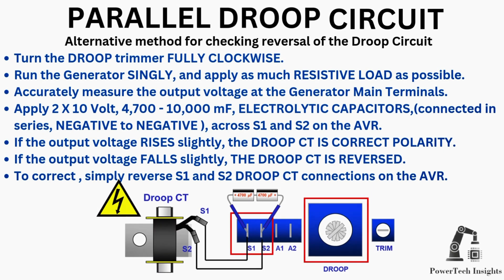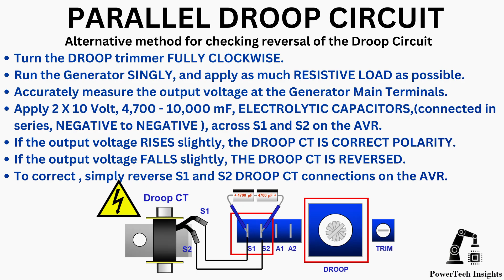Alternative method for checking reversal of the droop circuit. Turn the droop trimmer fully clockwise. Run the generator singly and apply as much resistive load as possible. Accurately measure the output voltage at the generator main terminals. Apply 2×10V, 4,700 to 10,000 microfarad electrolytic capacitors connected in series, negative to negative, across S1 and S2 on the AVR. If the output voltage rises slightly, the droop CT is correct polarity. If the output voltage falls slightly, the droop CT is reversed. To correct, simply reverse the S1 and S2 droop CT connections on the AVR.